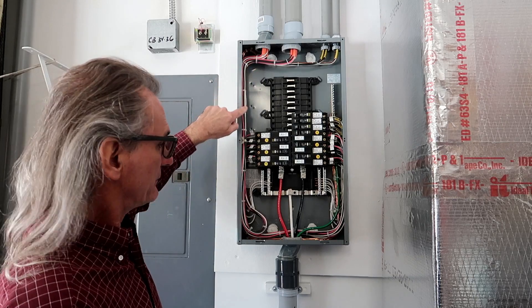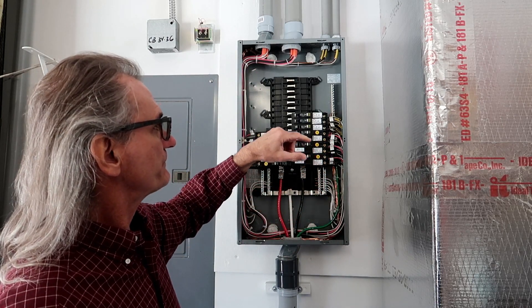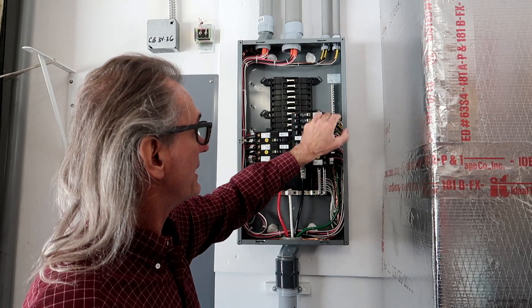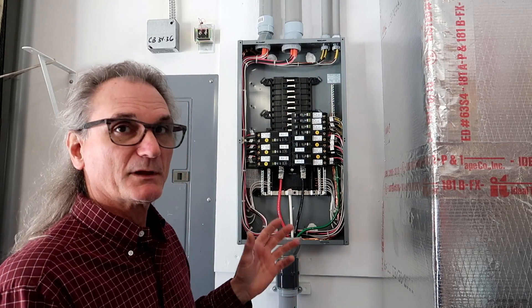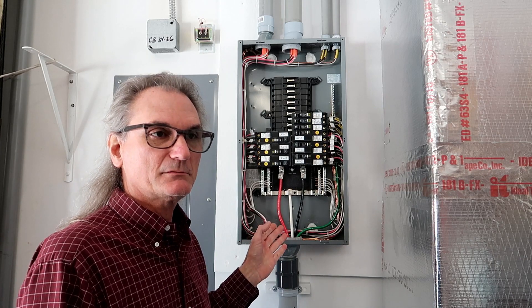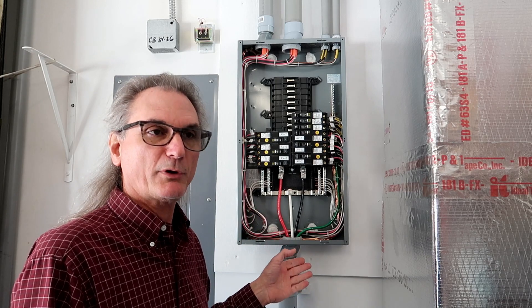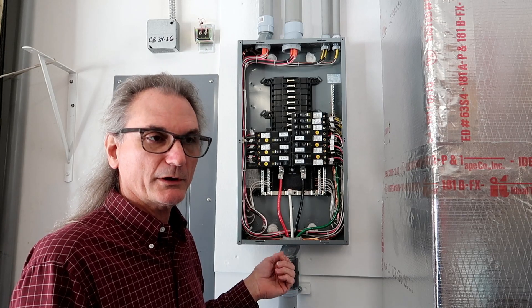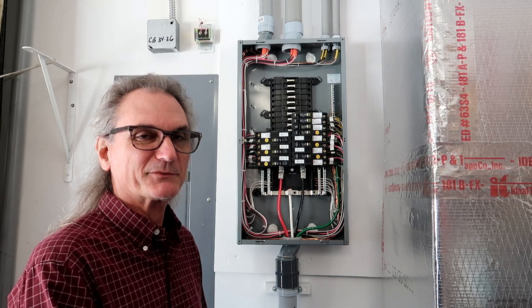I ran everything in this panel counterclockwise, and the reason is because this is a subpanel and it needs a ground bar — I put that ground bar in here. That ground bar takes up a lot of real estate. I also used combination arc fault circuit breakers. NEC 210.12 says I'm supposed to use them for new branch circuits if available. These arc faults were not available in Florida, so I ordered them from a circuit breaker company in Indiana or something like that.